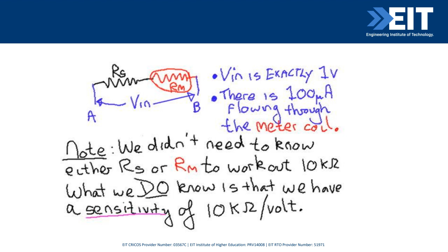Briefly, if it's a more sensitive meter with a 50 microamp full scale movement, we have more resistance. 20k per volt used to be pretty standard. If you see this on a meter, I want you to know what it actually means. A really expensive, hypersensitive meter could get up to 100 kilo ohms per volt. Why is this important? When measuring voltage, we don't want to put heavy loads on a circuit, so we try to get this value as high as possible.